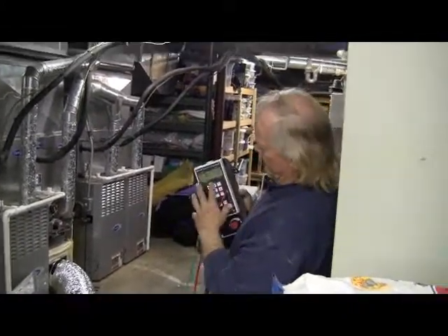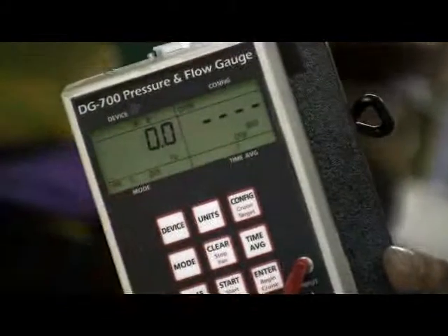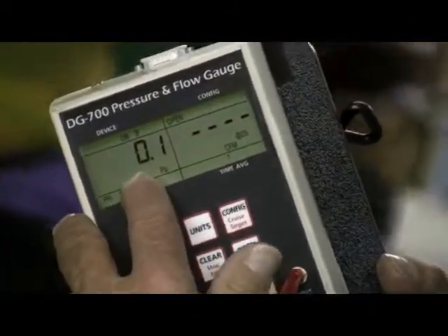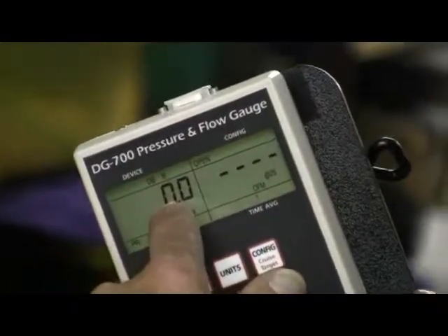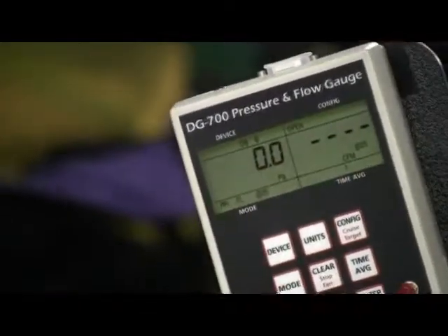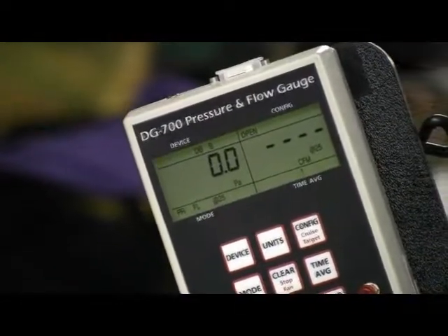We want to measure in this digital manometer the pressure that's in the ducting system in our A channel and the flow rate in our B channel. We want to be able to create a pressure differential between this room where we're standing and the ducts of 25 pascals ideally, and then measure the flow. So we're going to crank this up and see what we've got.